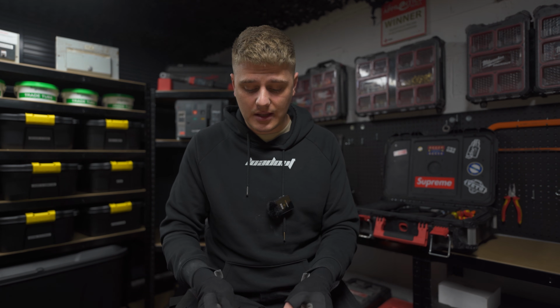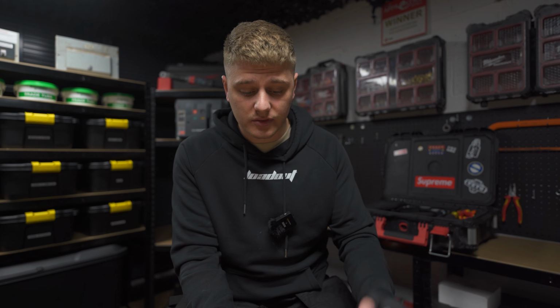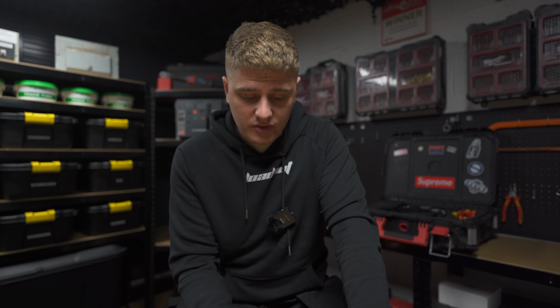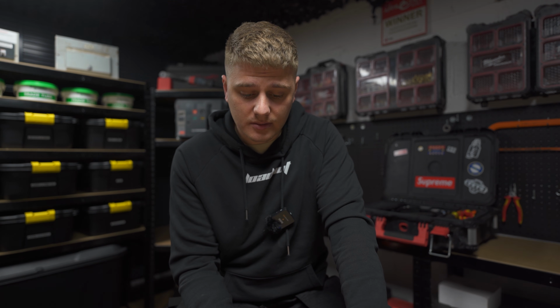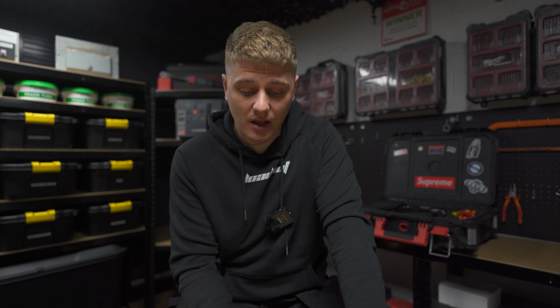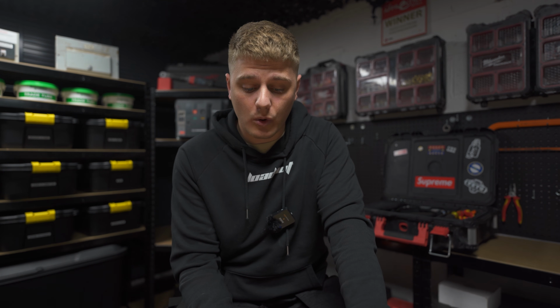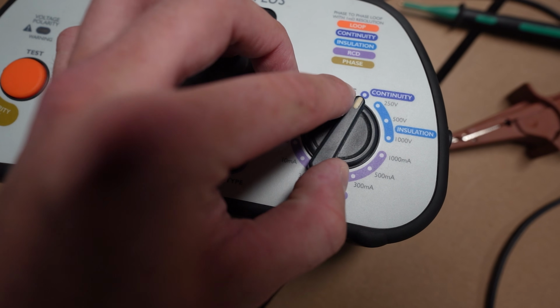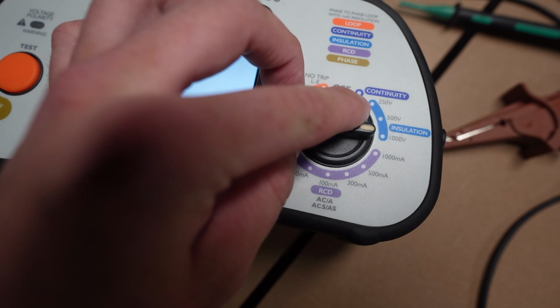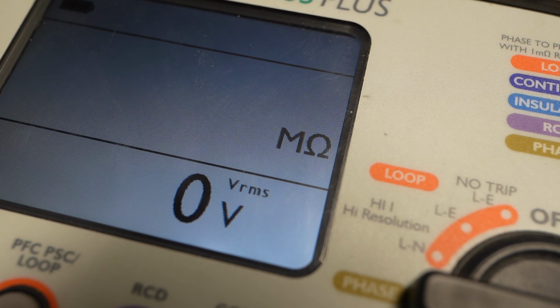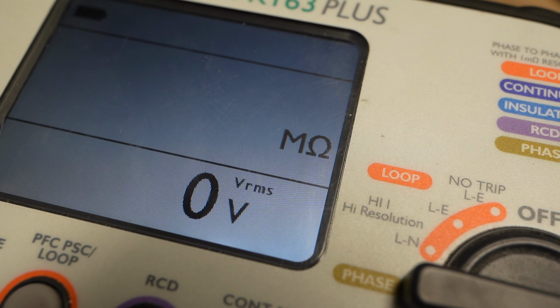Now, the IET actually posted some guidance on this, and the guidance suggested if the ohmic value between the suspected extraneous part and earth is greater than 22 kilo ohms, then the part in question is considered as unable to introduce a shock risk and, as such, won't require bonding. To measure this sort of reading, you're actually going to need an insulation resistance tester, and a reading of 22 kilo ohms will actually look more like 0.02 mega ohms.